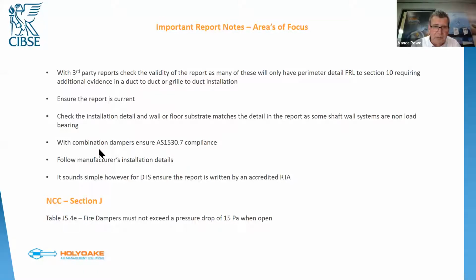Please ensure the report is current. The dates are on there. Again, that's absolutely critical. Check the installation detail of the wall or floor substrate. Make sure it matches the detail in the RIR report. There's a shaft wall system out there, for example, that is non-load bearing. So when you put a penetration through it, if you want to put a fire damper in there, you've got to support it in other ways. You can't support it in the shaft wall system. I've been talking to CSR about that more recently. So again, that detail is absolutely critical.